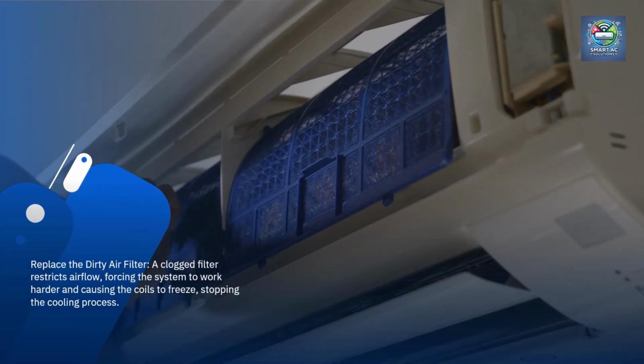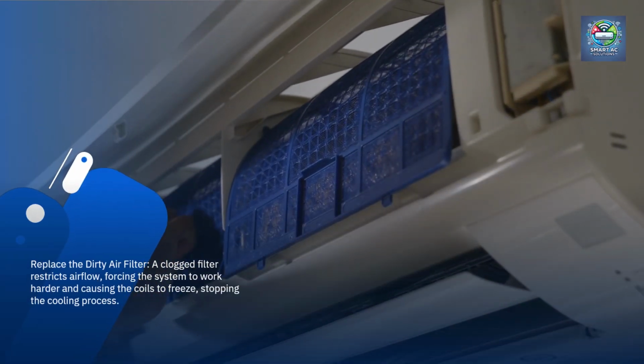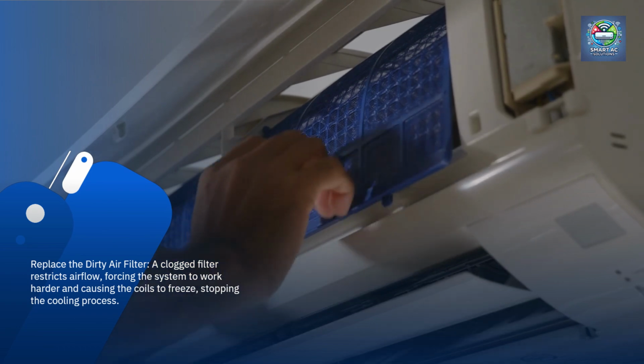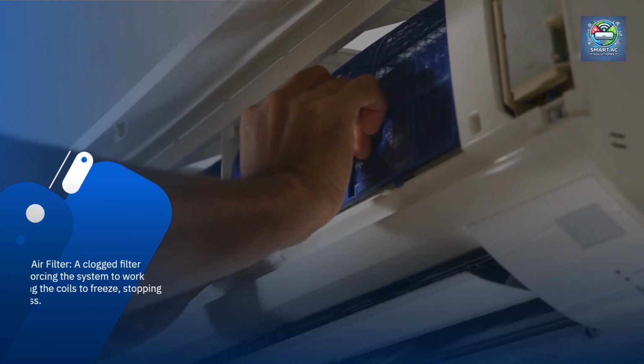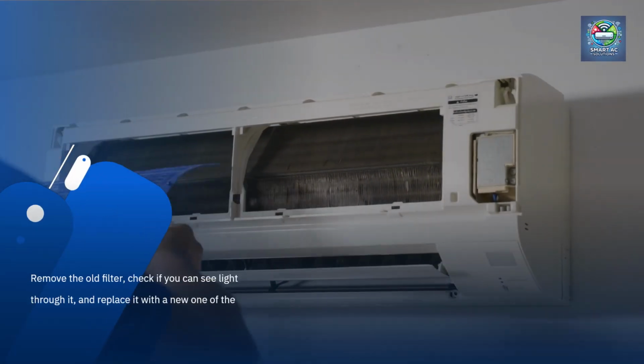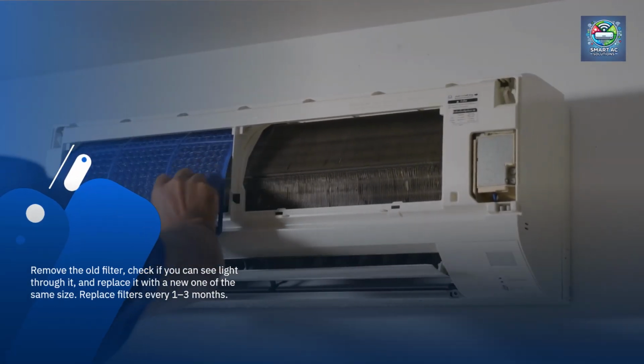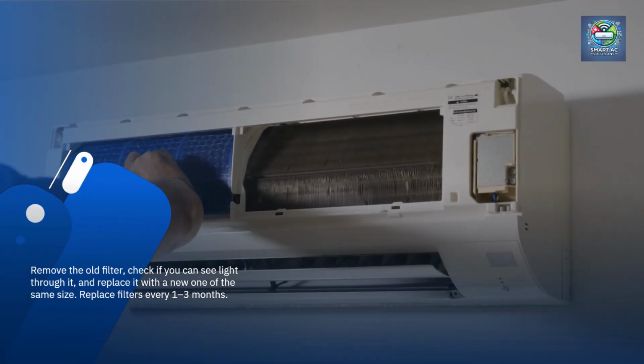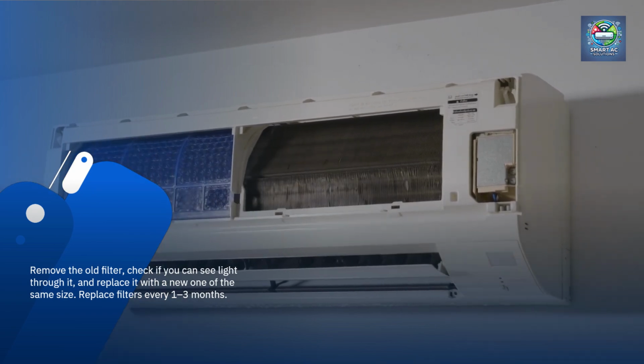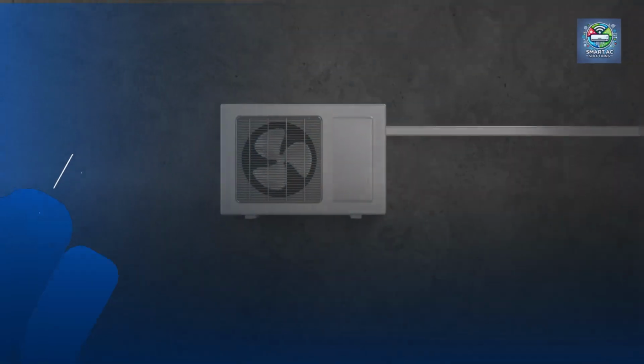Replace the dirty air filter. A clogged filter restricts airflow, forcing the system to work harder and causing the coils to freeze, stopping the cooling process. Remove the old filter, check if you can see light through it, and replace it with a new one of the same size. Replace filters every 1 to 3 months.